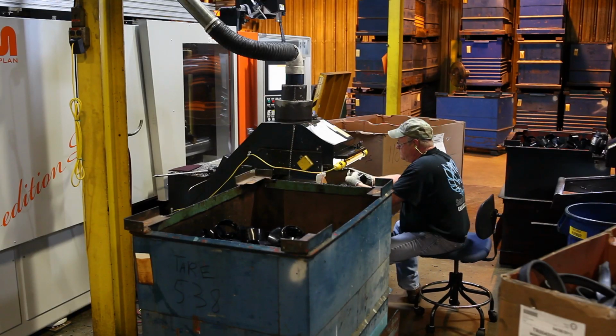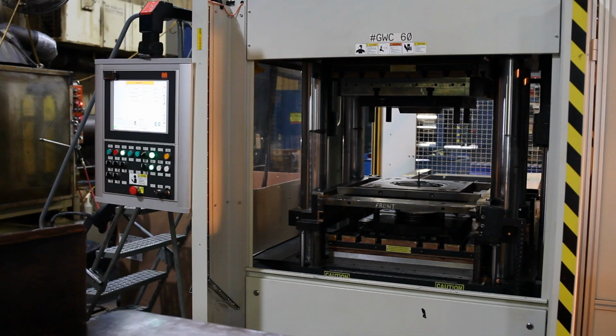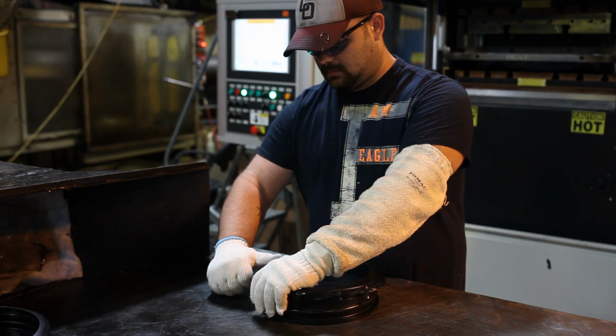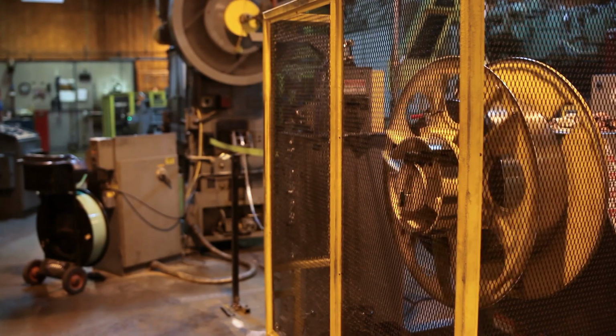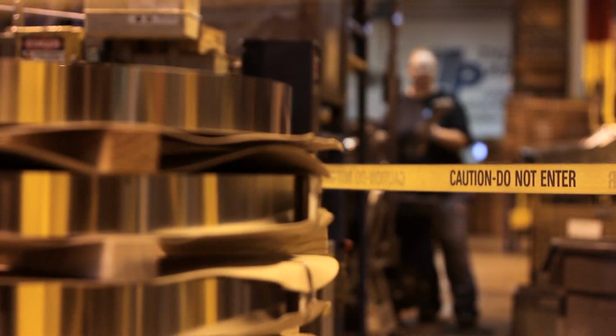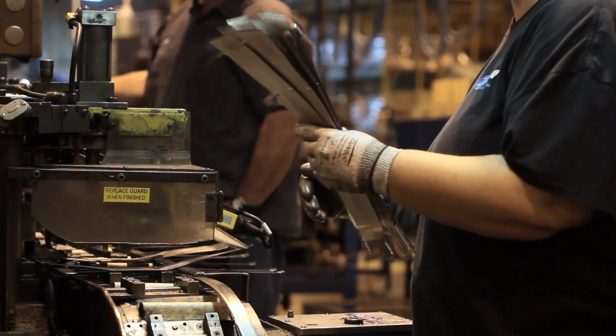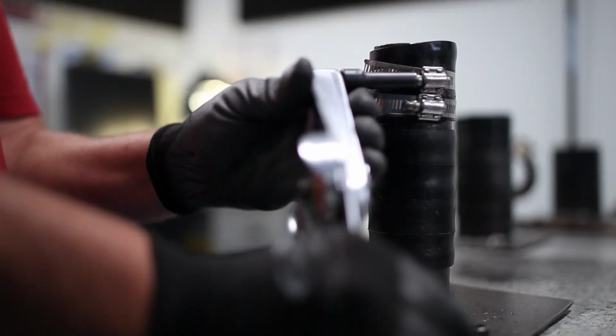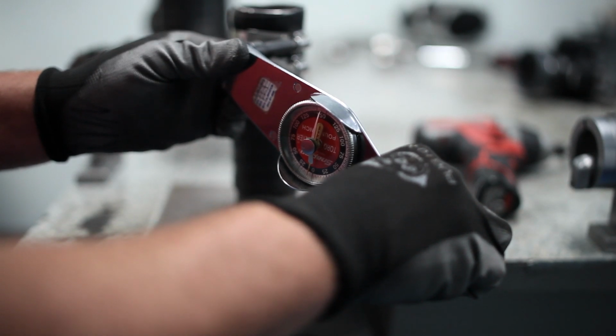At the core of all Tyler couplings are the gaskets. Designed by Tyler to provide multiple layers of leak-proof protection, these gaskets are made from genuine neoprene and are engineered to last decades, even in the most extreme environments. Stainless steel coupling shields are made with specially engineered corrugations to allow for secure sealing, even when joining pipe or fittings of slightly differing outside diameters. Tyler clamping bands are also made from 300 series stainless steel and are designed to provide a solid clamping force when torqued to the specified 60 or 80 inch-pounds depending on coupling size.